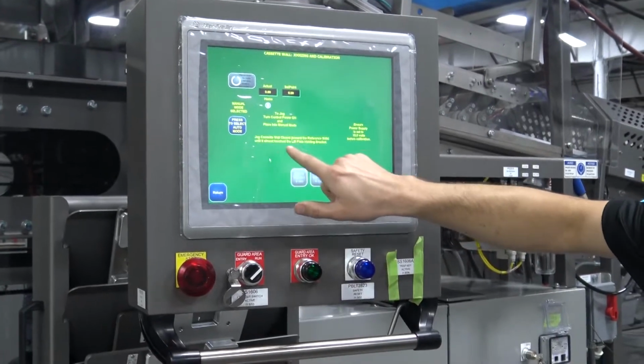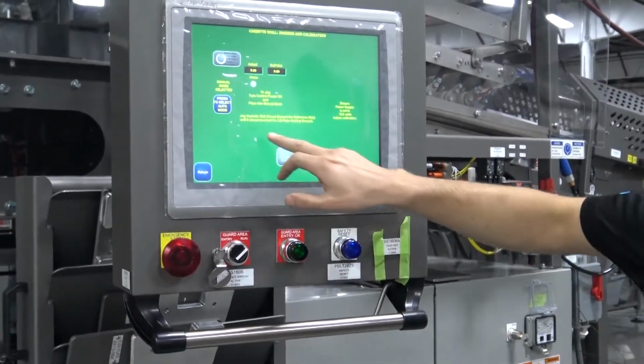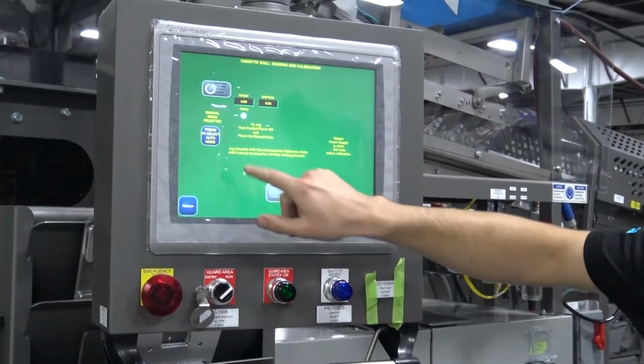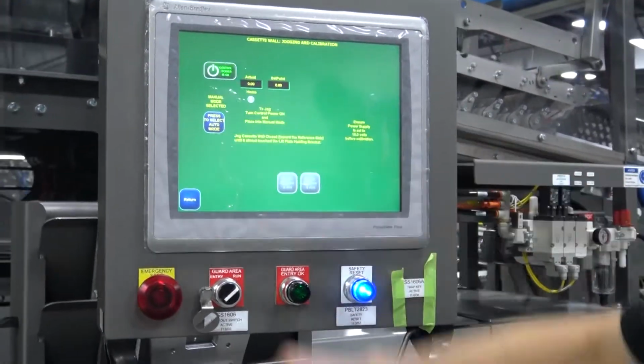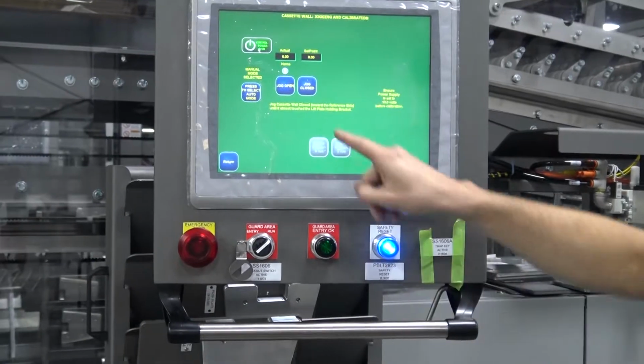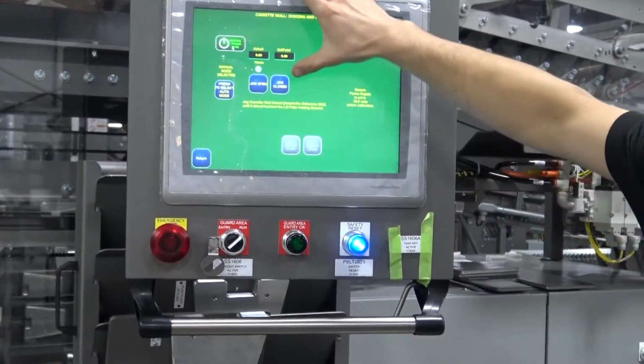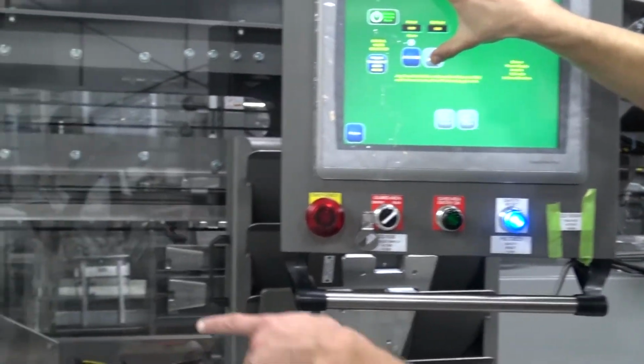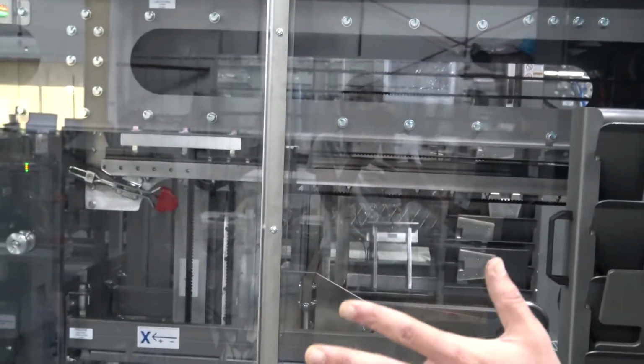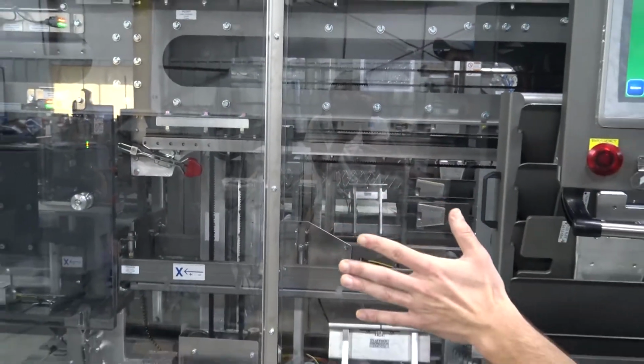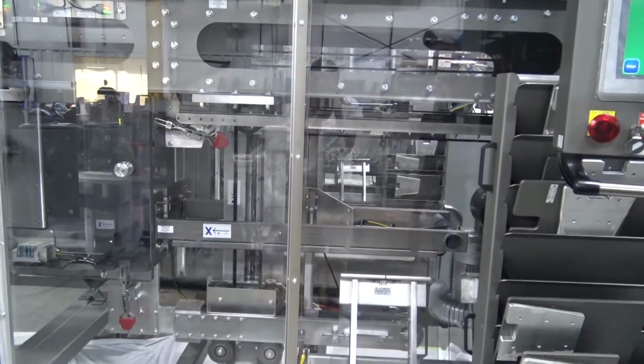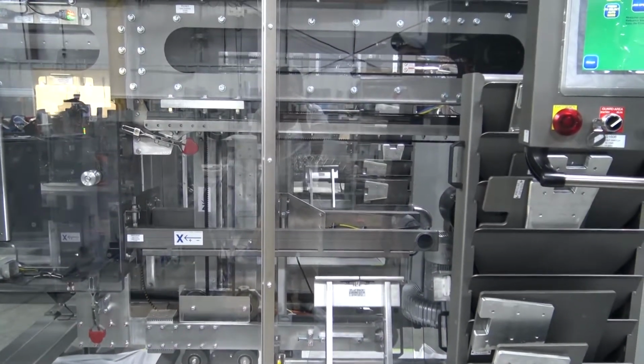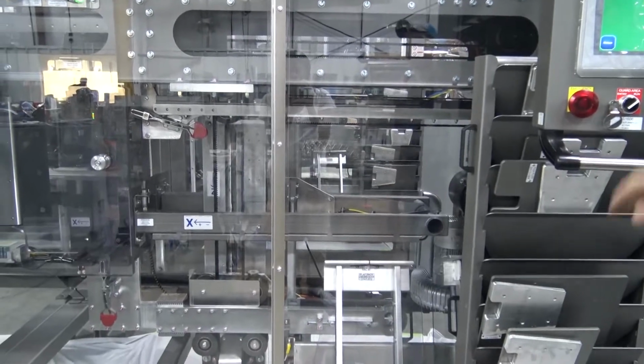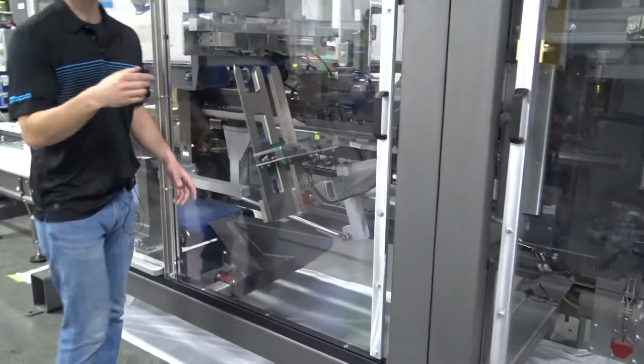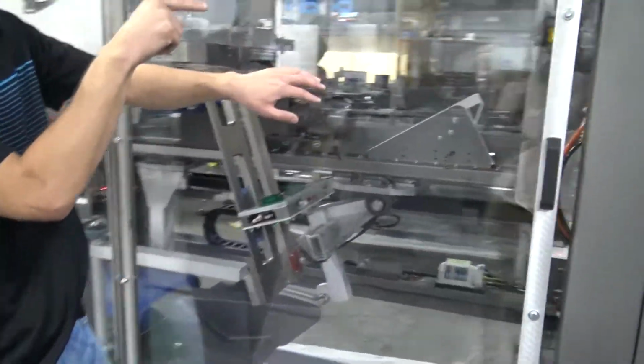Now it's asking me to jog the cassette wall closed until it almost touches the lift plate holding bracket. So I need control current to do that. So I return control current, and I have these jog buttons. I want to jog it closed. So I'm going to push this while I watch it. And you're going to watch that far cassette wall jog in. So I jog it in. And then while I'm in the middle of that, I'm going to come over here, and then we're going to look inside here.